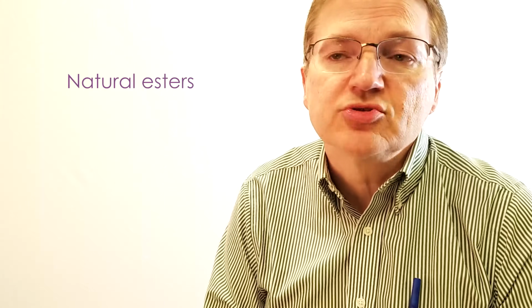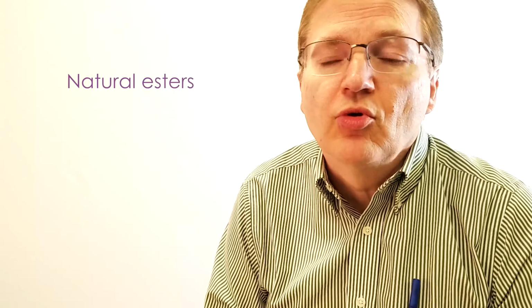Another fluid gaining very much in popularity recently is known as natural esters. These are basically made from vegetable oil, so natural ester is kind of the chemical name for vegetable oil. Some manufacturers make them out of soybean oil, others use corn oil, but they're properly processed to be pure enough to function electrically. They're gaining popularity because they're biodegradable, which is good if you have a spill, and they're also a high fire point fluid with the 300 Celsius minimum fire point.